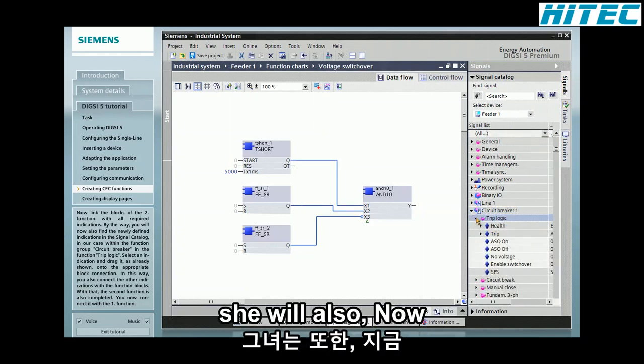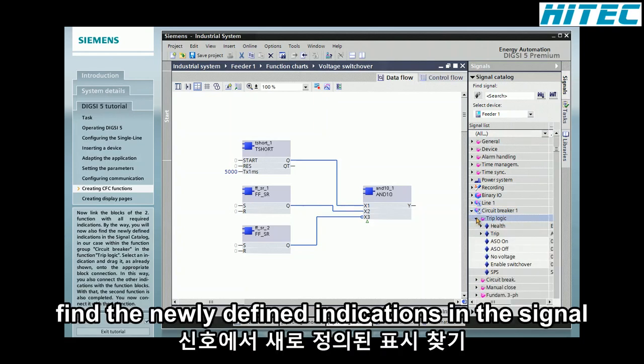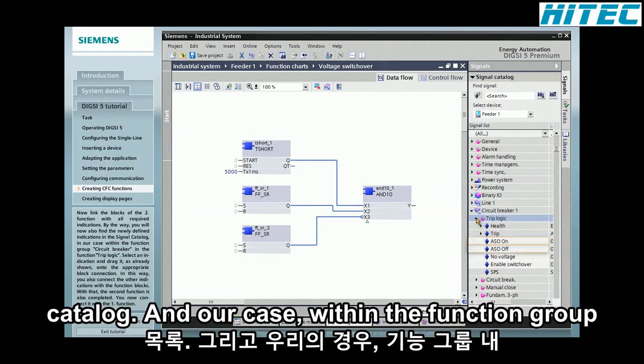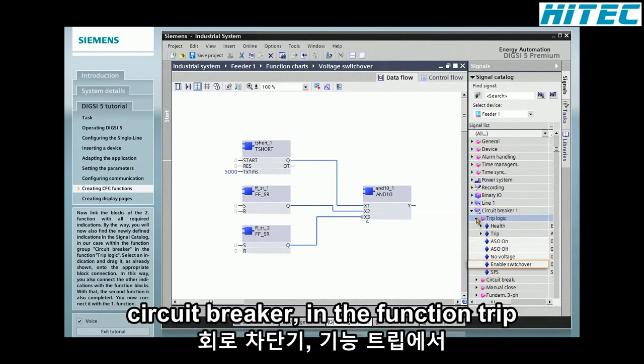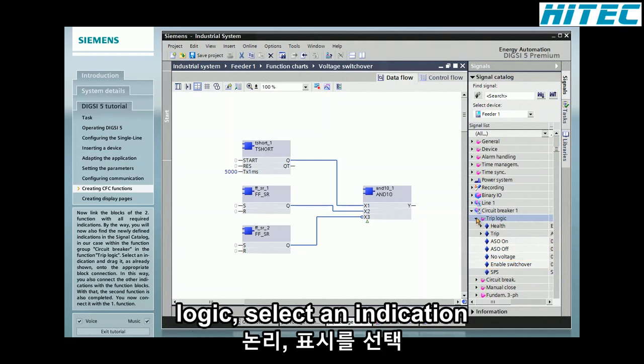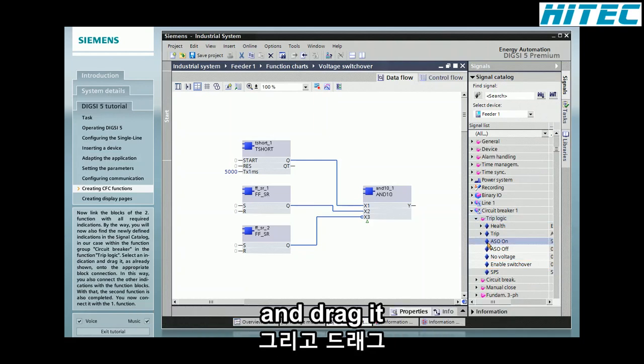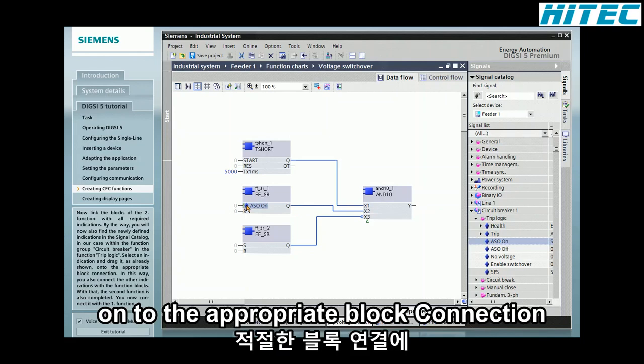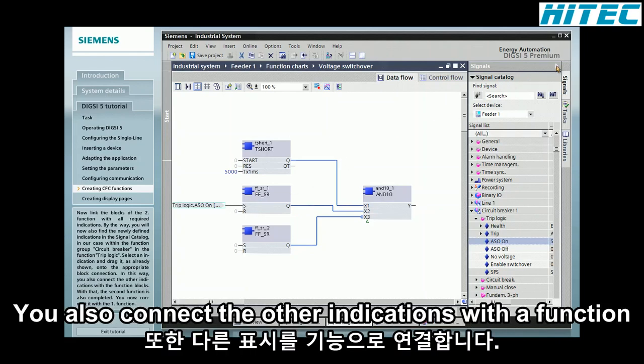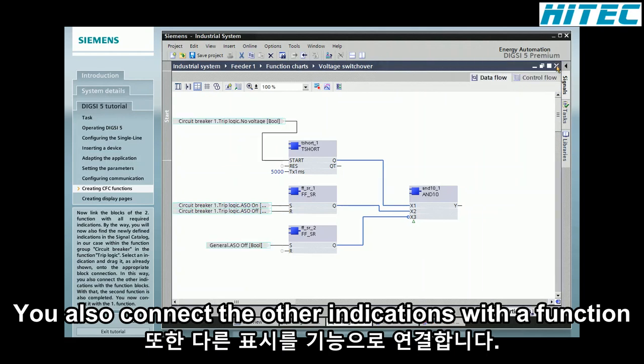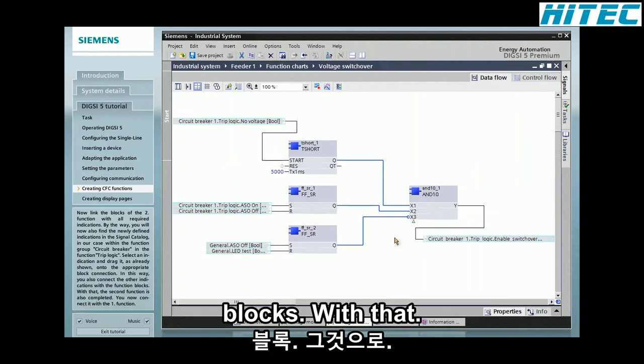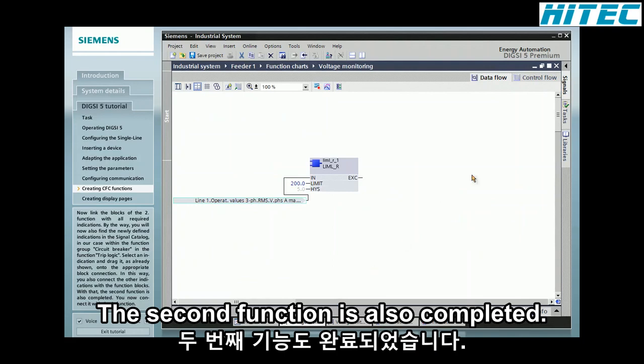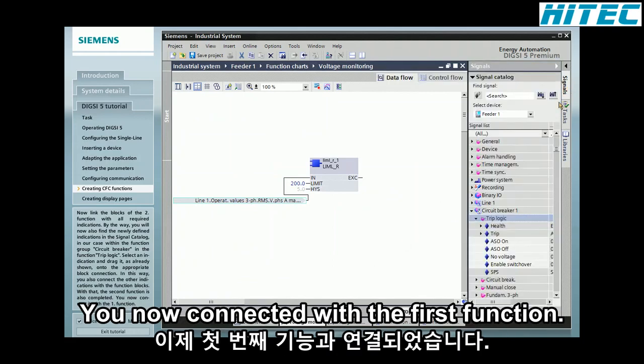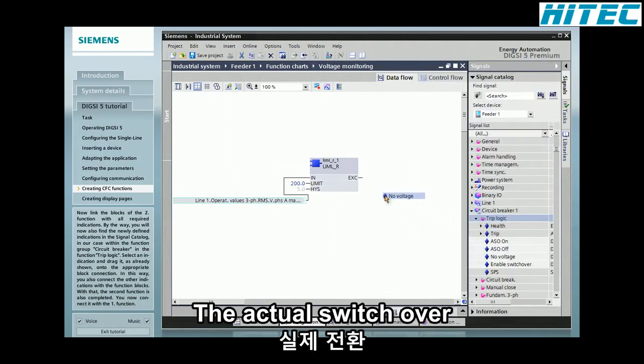By the way, you will also now find the newly defined indications in the signal catalog, in our case within the function group circuit breaker in the function trip logic. Select an indication and drag it, as already shown, onto the appropriate block connection. In this way, you also connect the other indications with the function blocks. With that, the second function is also completed. You now connect it with the first function.